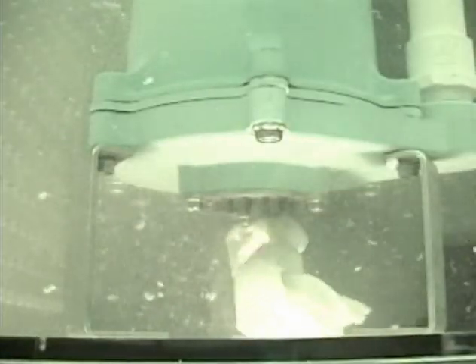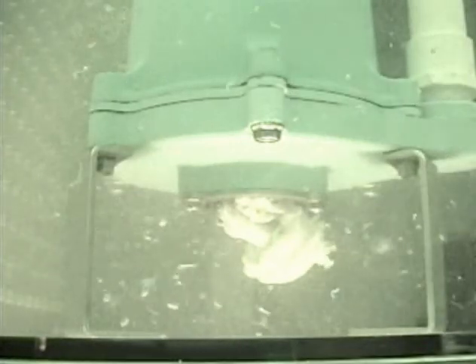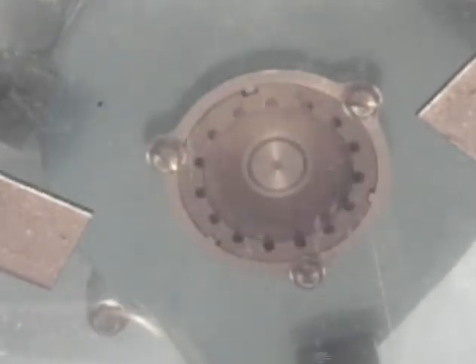Here, the Little Giant grinder is taking on knotted rags. We purposely stopped the pump in mid-grind and restarted it to show you how effectively the pump clears materials with each startup. That's accomplished by incorporating slots in the volute and keeping tight tolerances on the front end impeller clearance.